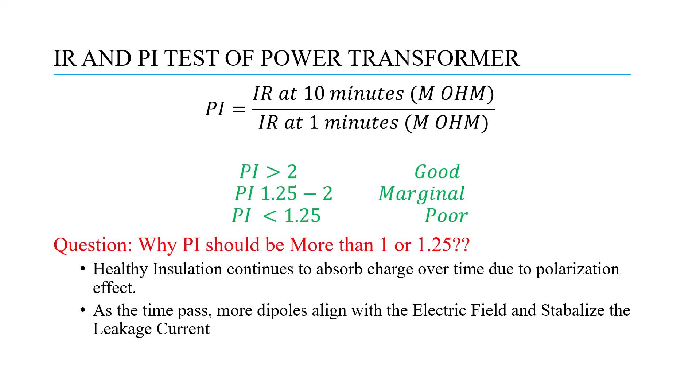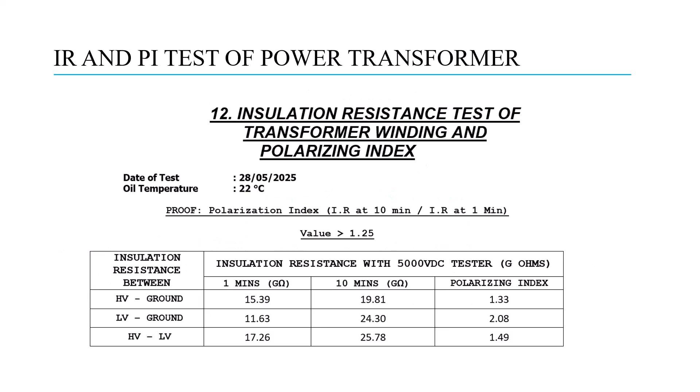The answer is that healthy insulation continues to absorb charge over time. As we inject voltage for 10 minutes, healthy insulation absorbs the charge due to the polarization effect. As time passes, more dipoles align with the electric field and stabilize the leakage current. Therefore, the leakage current is reduced and the insulation resistance gets strengthened with time, since we are injecting DC voltage.